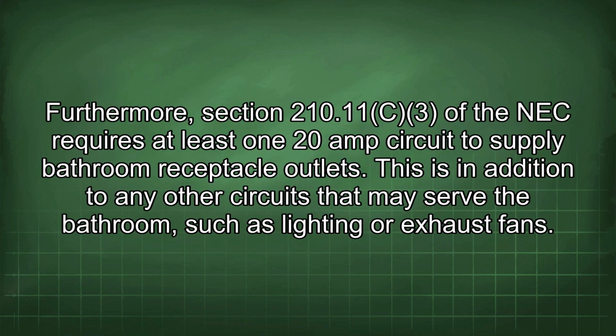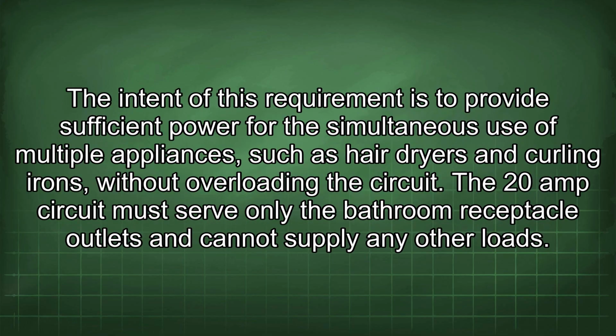Furthermore, Section 210.11(C)(3) of the NEC requires at least one 20-amp circuit to supply bathroom receptacle outlets. This is in addition to any other circuits that may serve the bathroom, such as lighting or exhaust fans. The intent of this requirement is to provide sufficient power for the simultaneous use of multiple appliances, such as hair dryers and curling irons, without overloading the circuit.